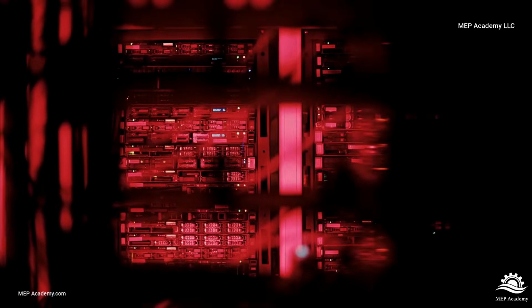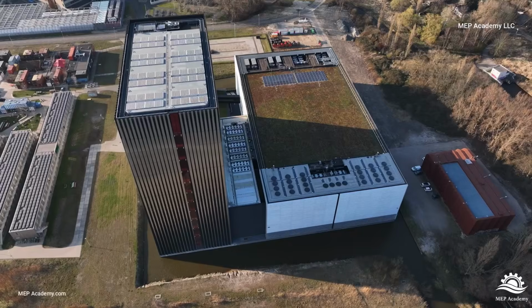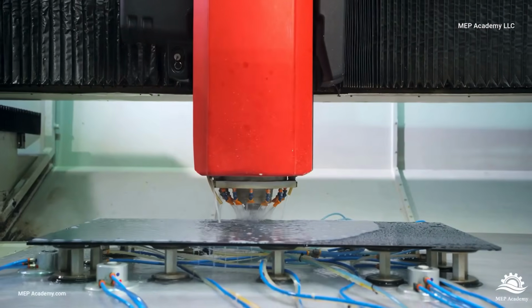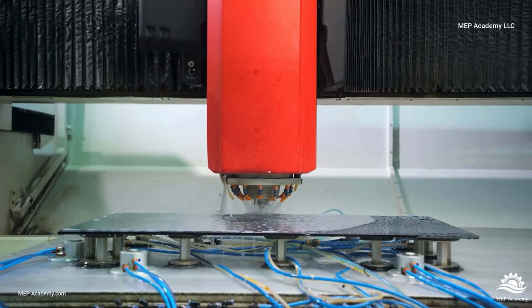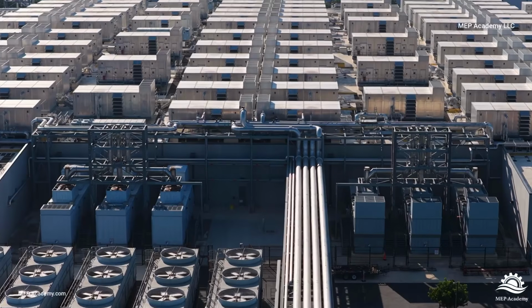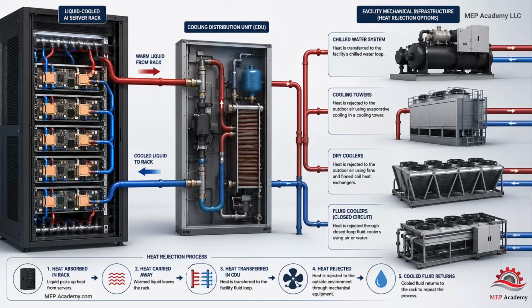Removing heat from the server is only half the battle. The heat still has to leave the building. Once heat is transferred into the liquid cooling system, it ultimately moves into the facility's mechanical infrastructure. That may include chilled water systems, cooling towers, dry coolers, fluid coolers, or other heat rejection equipment. The exact configuration varies from one facility to another, but the principle remains the same.